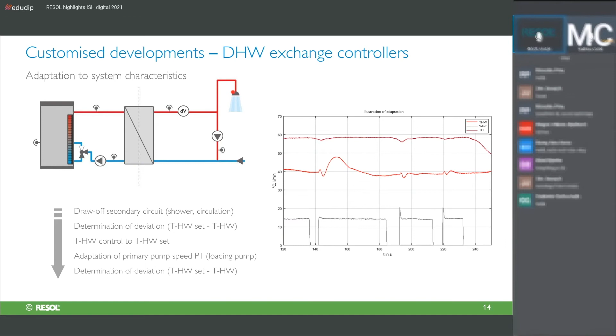Very similar to the freshwater controllers are the controllers for heat transfer stations. The special feature here is that in combination with the freshwater part, the heating part is also taken over and included in the controllers. And with this controller concept that we offer here, the control of a weather compensated heating circuit is also possible, even with a room influence or exclusively via the indoor temperature. We offer 3 different control modes with which we can control the heating circuits then. There are also several pre-programmed functions, and a remote access via a room control unit is also possible. This can easily be set then in the controller if it is necessary.